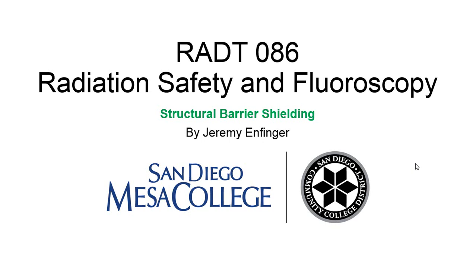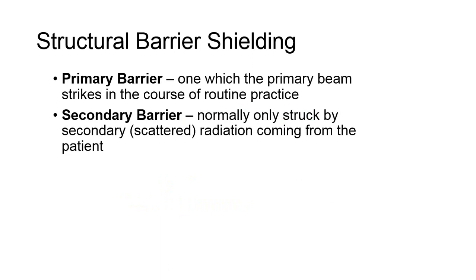Structural Barrier Shielding: Any structural barrier, including walls, floors, the ceiling, and windows, can protect you from radiation. These are generally divided into primary and secondary barrier categories. A primary barrier is one which the primary beam strikes in the course of routine practice. A secondary barrier is normally only struck by secondary or scattered radiation coming from the patient.